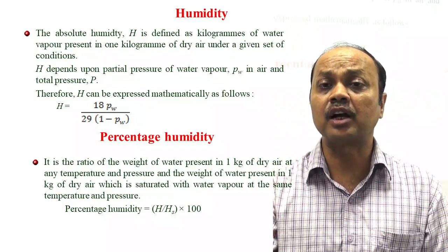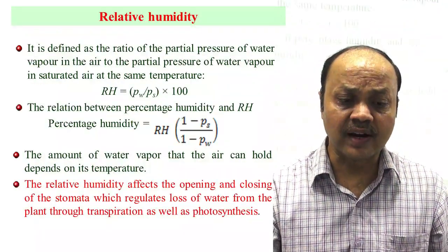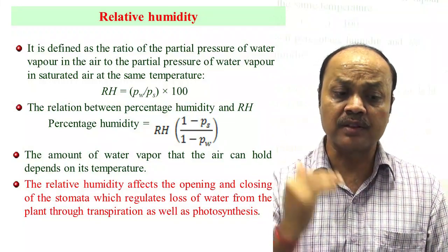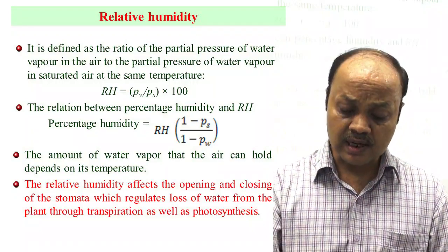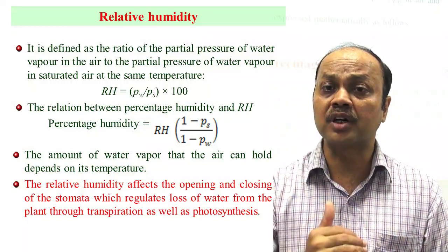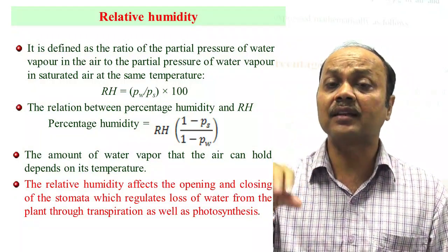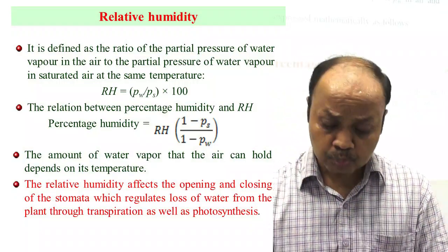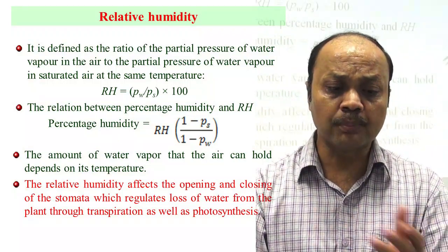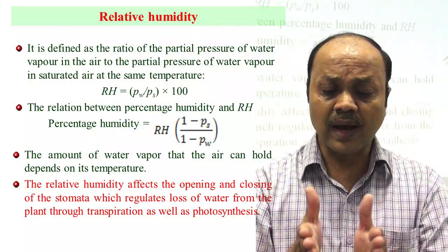Relative humidity is simply defined as the ratio of partial pressure of water vapor in the air to the partial pressure of water vapor in saturated air — that is Pw by Ps. So actual humidity h divided by saturated humidity h-s corresponds to Pw by Ps. If you know Pw and Ps, you can calculate relative humidity as well as percentage humidity.